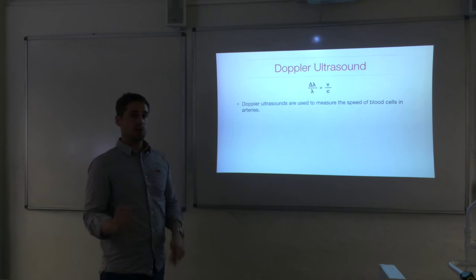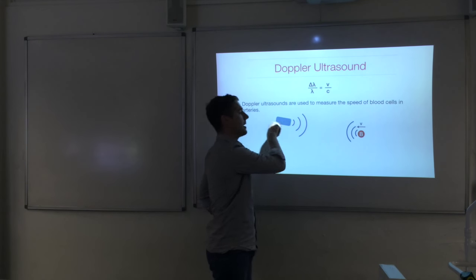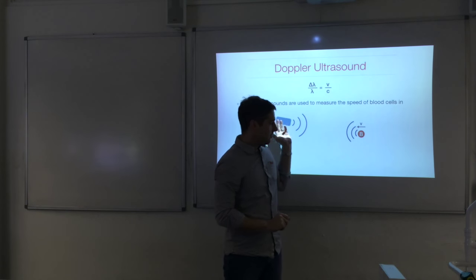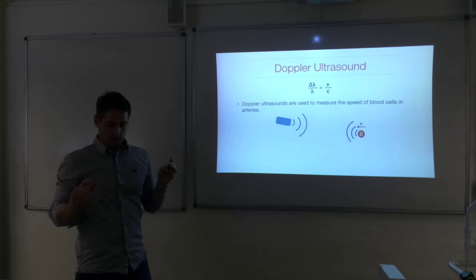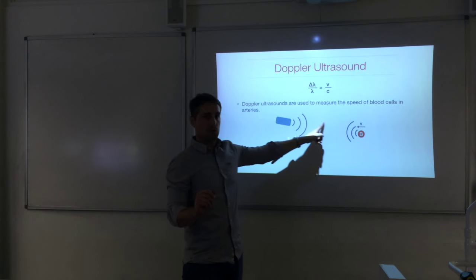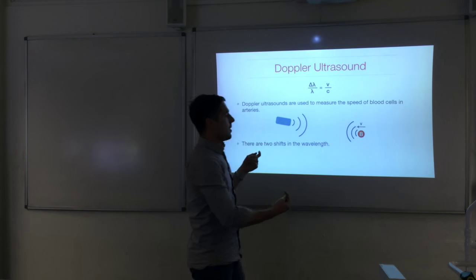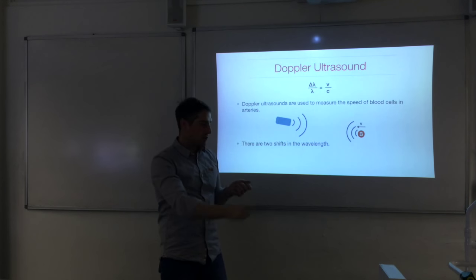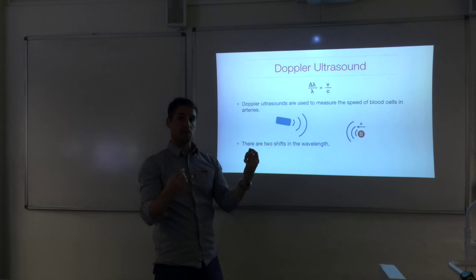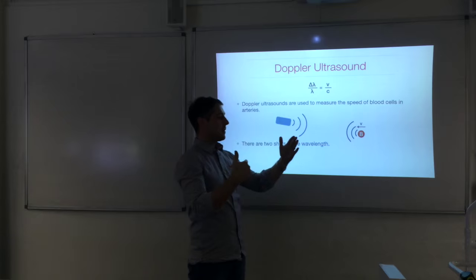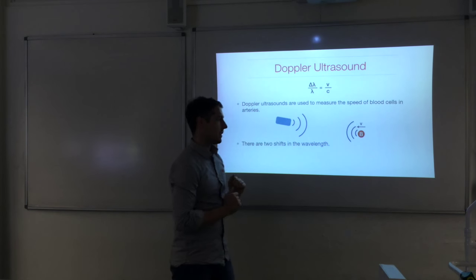Doppler ultrasound measures the speed of blood cells in arteries. The transducer transmits ultrasound aligned toward the moving blood cells. When the blood cells reflect the ultrasound back, you get a shifted wavelength. There are actually two shifts: first, when the ultrasound is produced by the transducer, the blood cell acts as an observer moving toward the source, so the received wavelength is reduced. Second, when it reflects, the blood cell acts as a moving source, shortening the wavelength again.